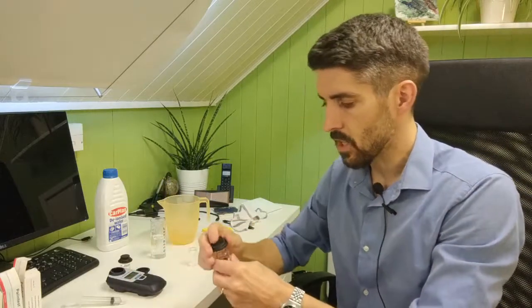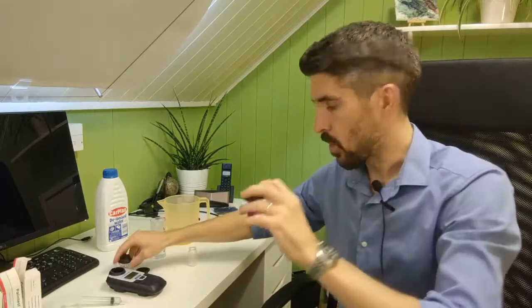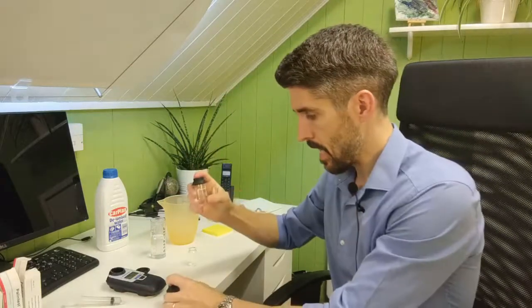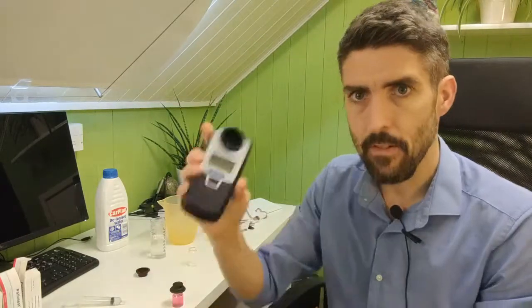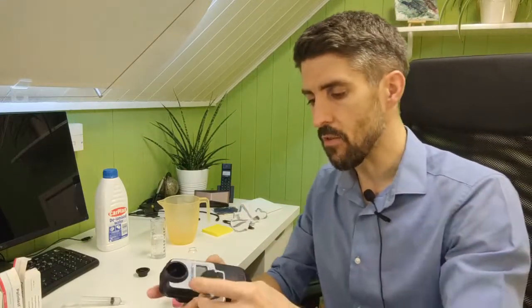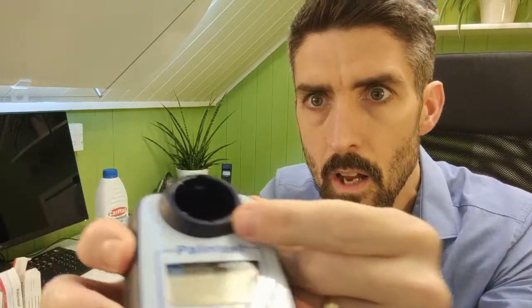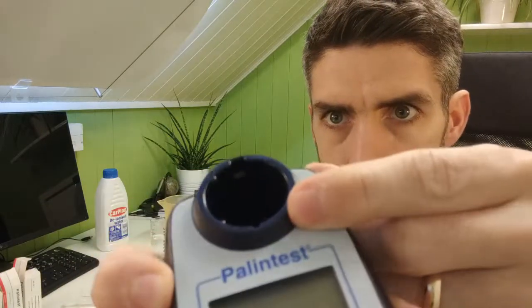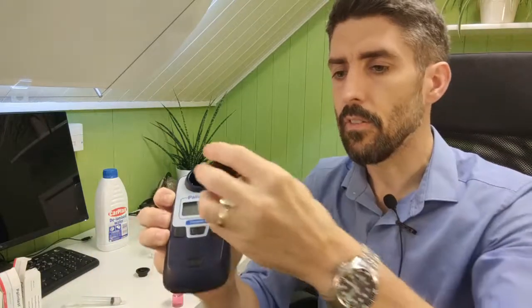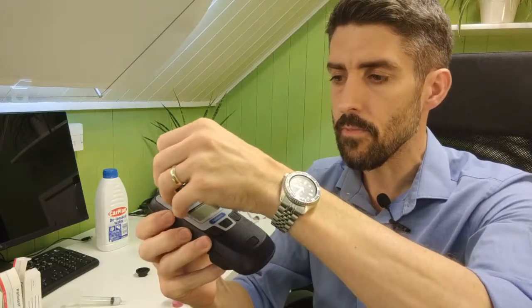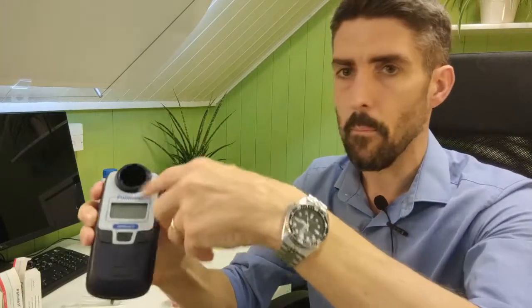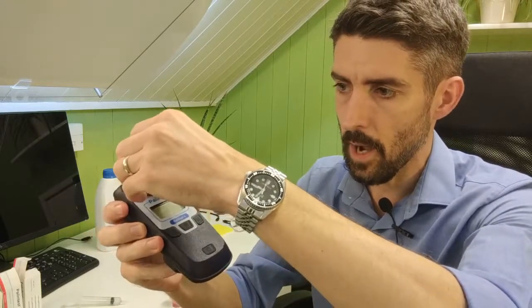So once you're ready, so you've got your sample and you've got your blank, what you do is you put the blank in first, because with these photometers they need to be zeroed. Now what you've got on the test tube is a diamond shape that needs to line up with the triangle on the front of the circular part that you put the test tube in. They need to line up.